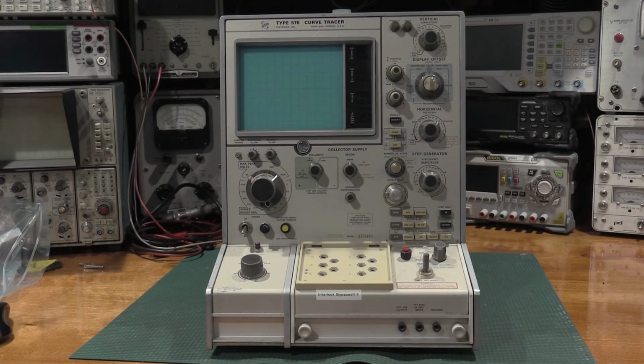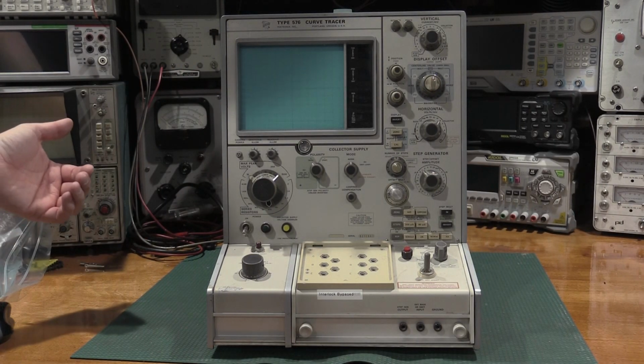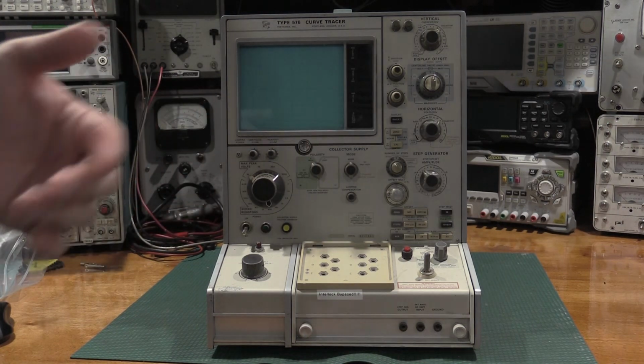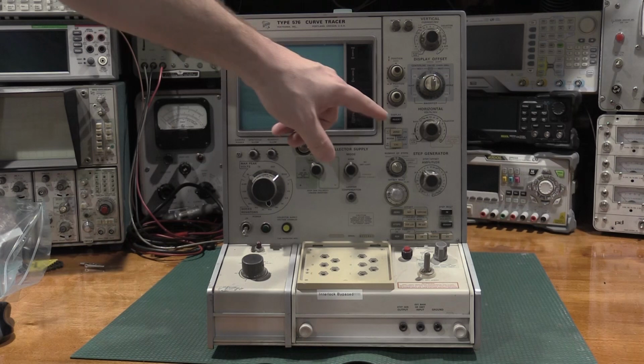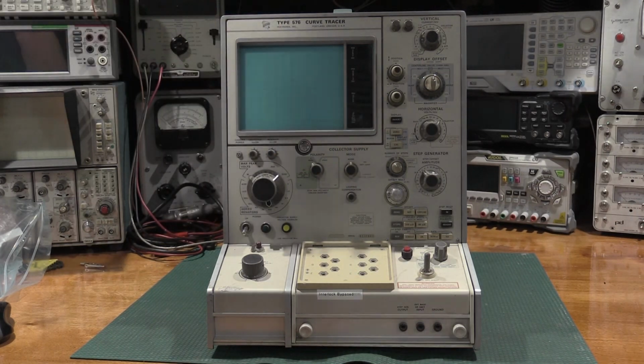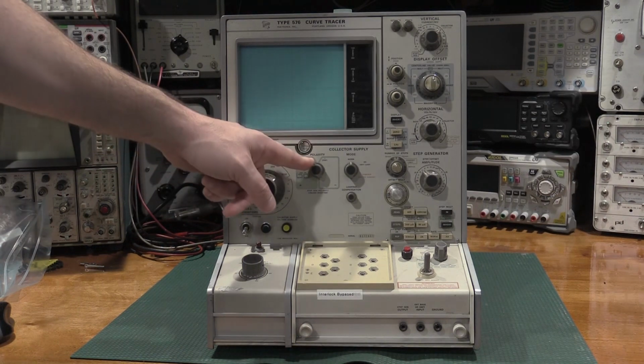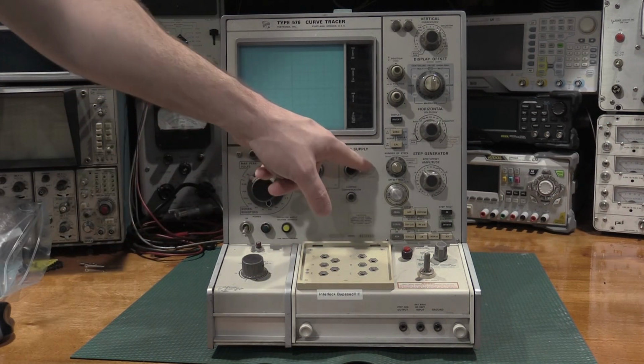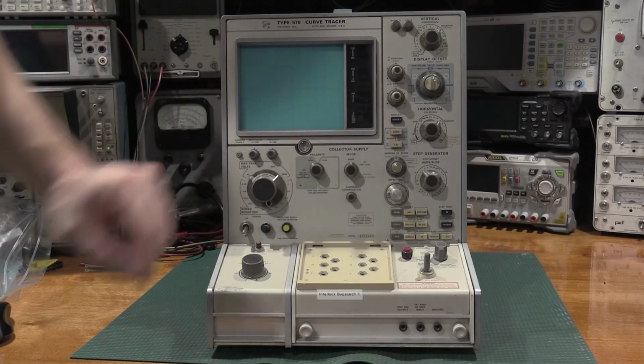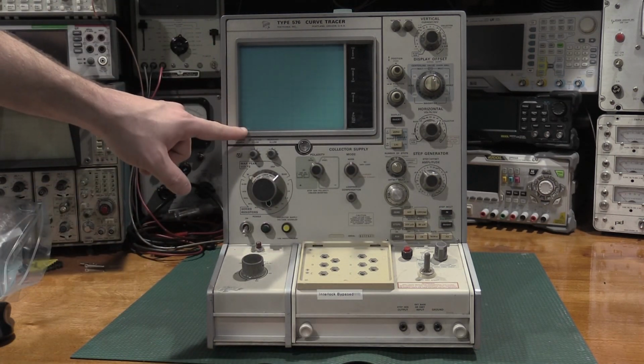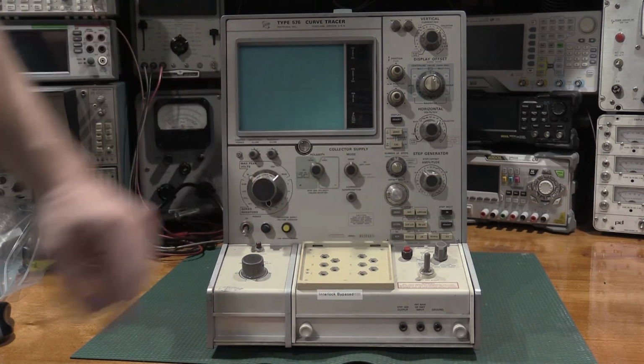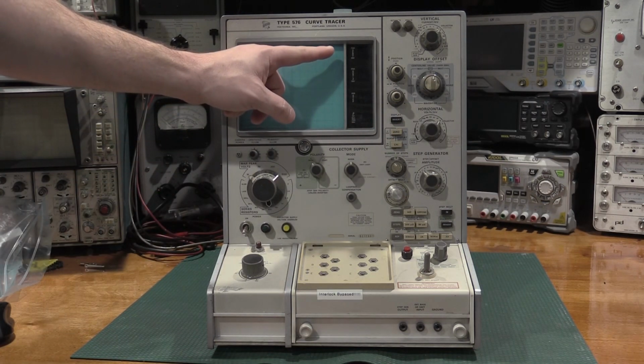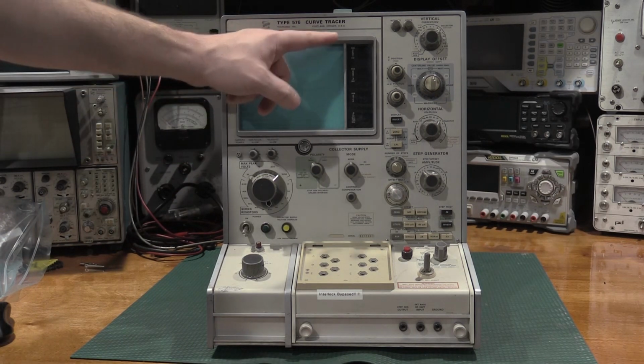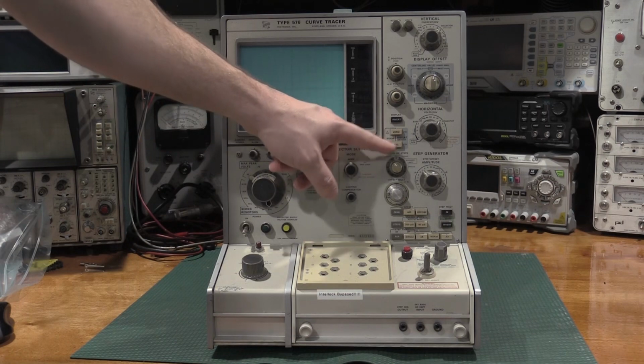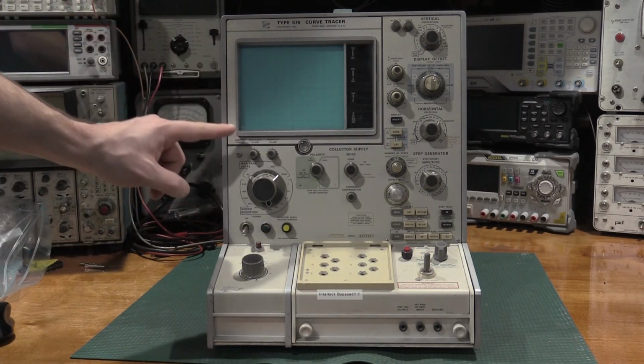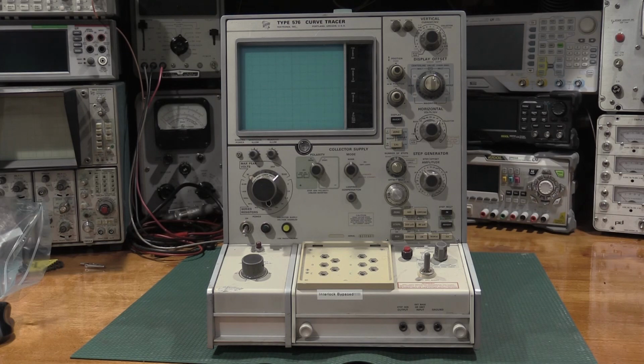One other quick test, if you do have a unit and it does pass all of the inspections to see how well it might have been taken care of, is you can do a quick test with the 0 cal and invert buttons. So what you can do is set it up in NPN mode where it's sweeping, normal mode, not DC. And then if you hit 0 and use the position controls to line it up at the bottom corner, and then you hit calibrate, it should jump to the top corner. If between the 0 and the calibrate buttons you can bounce it between those 2 points, the unit's in pretty decent calibration at that point.